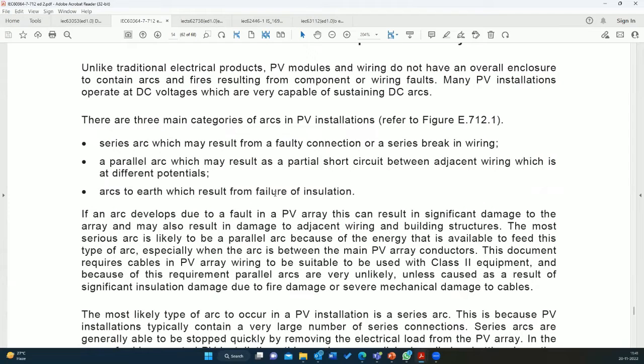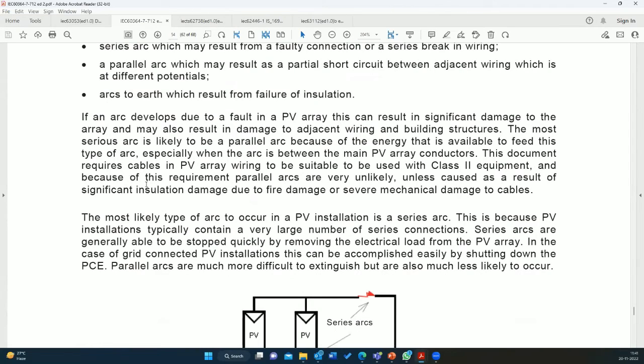from failure of insulation. Further, if an arc develops due to a fault in the PV array, this can result in significant damage to the array and may also result in damage to adjacent wiring and building structure. The most serious arc is likely to be the parallel arc because of the energy that is available to feed this type of arc, especially when the arc is between the main PV array conductors.